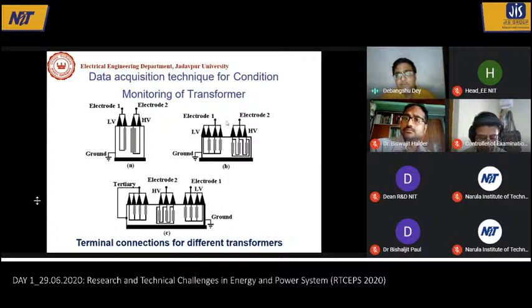Similarly, here also, low voltage and high voltage winding are just shorted and they are providing two electrodes. So from a circuit point of view, if we give some voltage here across electrode 1 and electrode 2, it is basically a capacitor charging phenomenon. Because the low voltage winding and high voltage winding are copper conductors, and in between them there exists certain insulation. We are trying to find out the condition of this insulation.